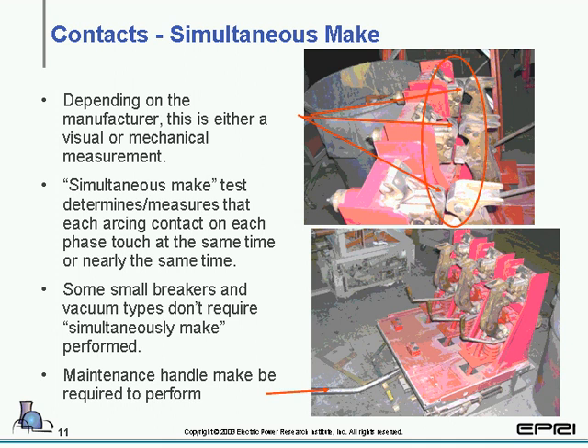The next one we're going to take a look at is simultaneous make. Along with the items that are listed, simultaneous make is when all three phases touch at or approximately the same time. And in the very bottom slide, you'll see a little red arrow. That arrow is pointing to a maintenance handle. Some designs, you actually have to install a maintenance handle and capture the closing springs to perform this task.